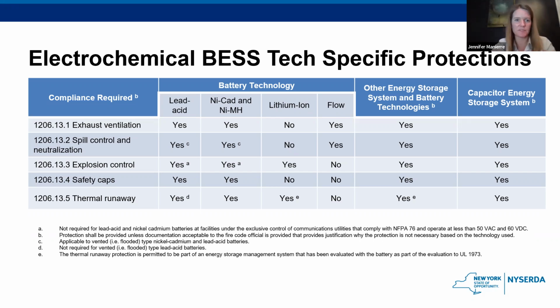And whether or not those sections apply to a specific type of battery is shown in the 4 columns to the right of that. So for example, you'll see the exhaust ventilation requirement, like we just mentioned a minute or two ago in conversation, is absolutely required for lead acid batteries because they do off-gas as part of their normal operations. It is not required over in the 3rd or 4th column there for lithium ion. They are not required to have exhaust ventilation because they don't produce exhaust as part of the normal course of their charging and discharging.